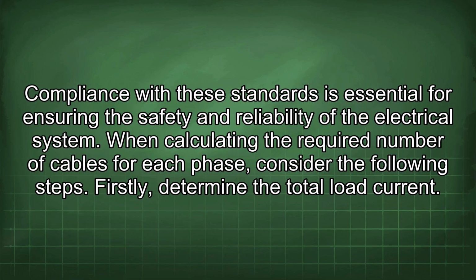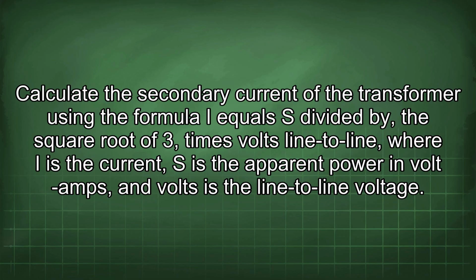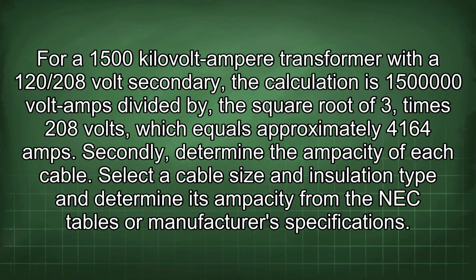When calculating the required number of cables for each phase, consider the following steps. Firstly, determine the total load current. Calculate the secondary current of the transformer using the formula I equals S divided by the square root of 3 times volts line to line, where I is the current, S is the apparent power in voltamps, and volts is the line-to-line voltage. For a 1500 kVA transformer with a 120/208 volt secondary, the calculation is 1,500,000 voltamps divided by the square root of 3 times 208 volts, which equals approximately 4,164 amps.